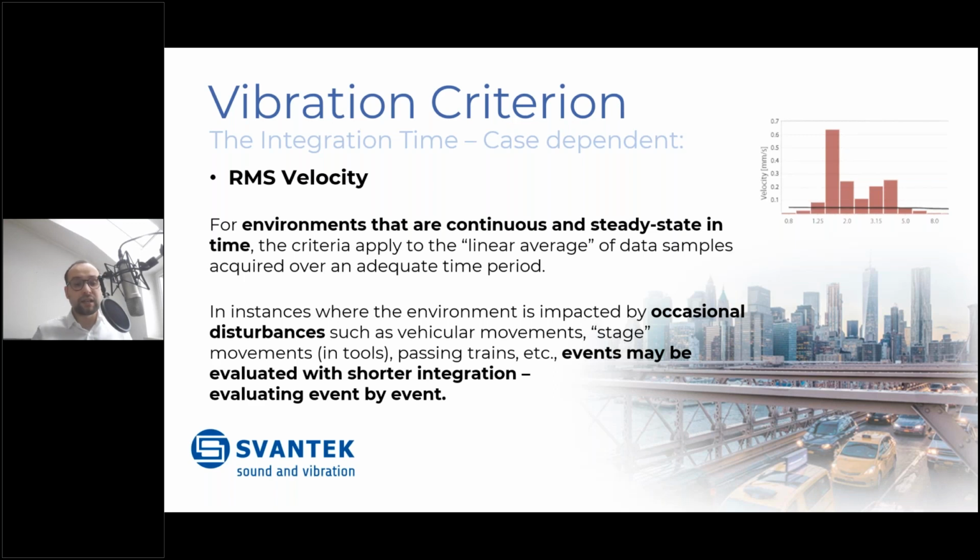There is nothing happening randomly. But if you have an event-based scenario where there are peaks and short occurrences, then you must have the ability to use a short integration period, because otherwise you will average out the very level that you're trying to measure.